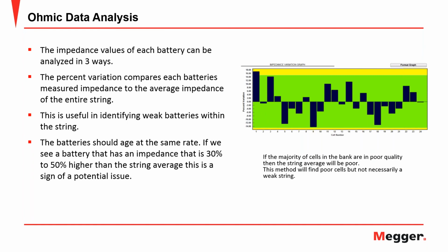And that battery could be going bad, or again, it could be a strap issue, or we could have very unbalanced voltages. But all of these can lead to these. You may find you actually have a bad battery, but you do want to do the due diligence of the troubleshooting.